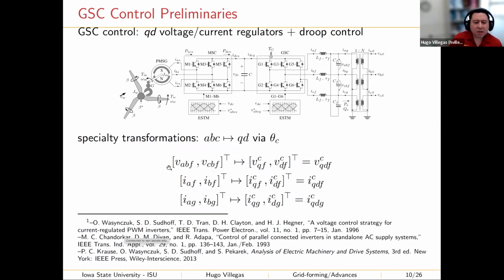So here I'm using special transformations. For example, I'm transforming line-to-line voltages, VABF and VCBF, into QD directly. The same for the currents IA and IB of the filter at the terminals of the inverter into QD, and the same for the current that is observed at the grid side, or the low voltage side, of the transformer. This current is actually very important, the IAG, IBG, and ICG, or its transformed version QDG, because this current is used for feed-forward control.